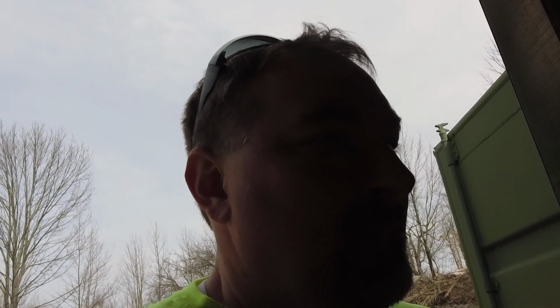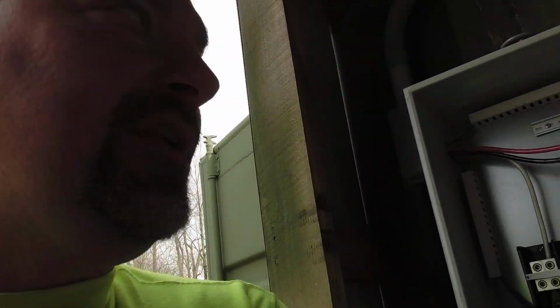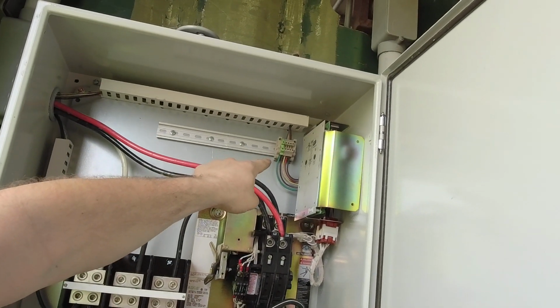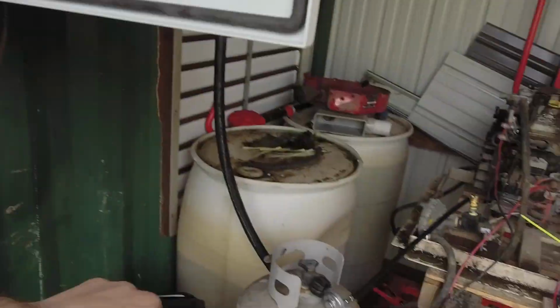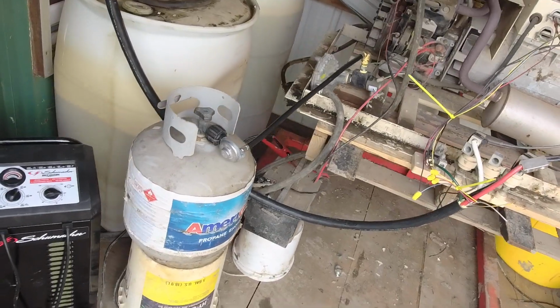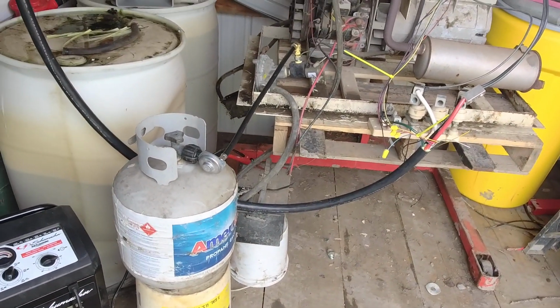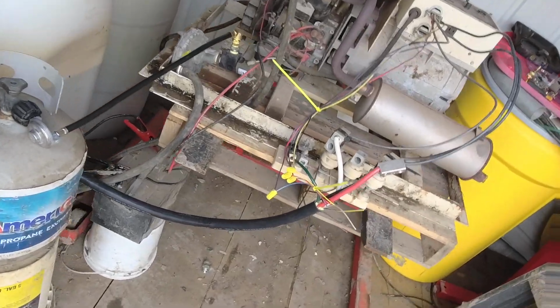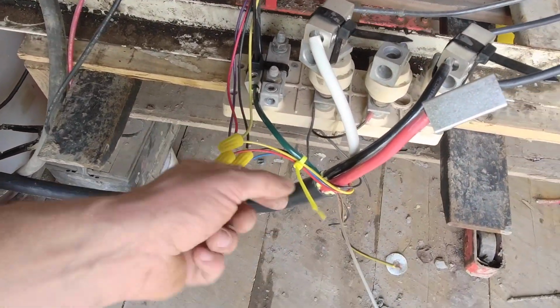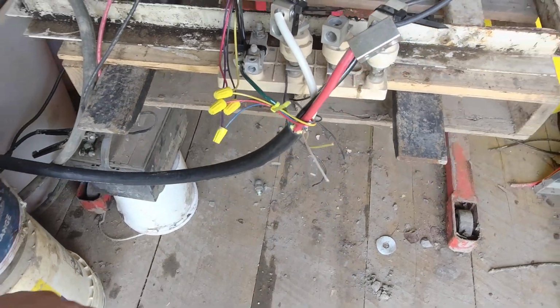I'm still on the fence. The relays I have in hand right now are 12-volt coil, but I'm not sure whether I want to use 12-volt or change those relays into a 120-volt coil. If I go with a 12-volt coil, I need to get 12 volts from somewhere. I do have 12 volts coming in here from the generator itself, via the battery line, but the issue is these wires are like 18 or 16 gauge. Yeah, they're 18 gauge.